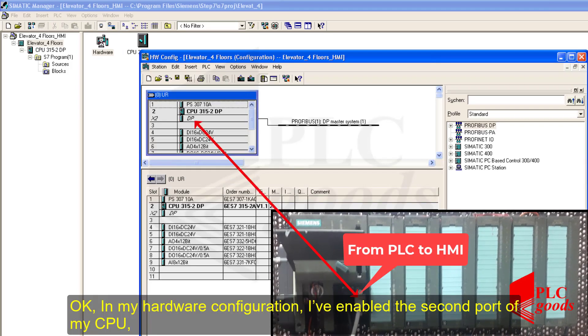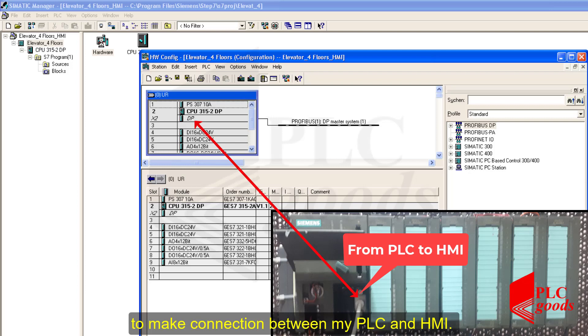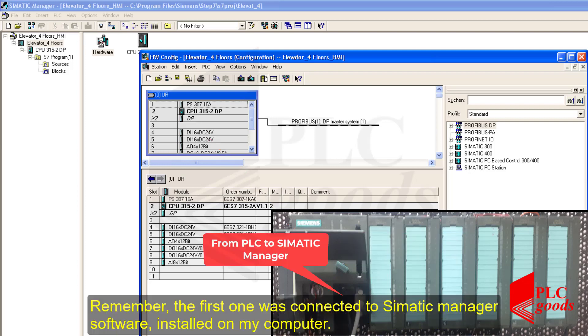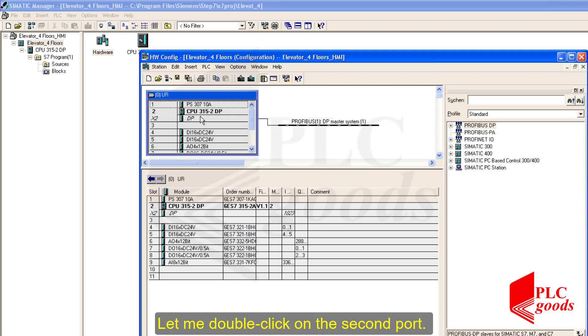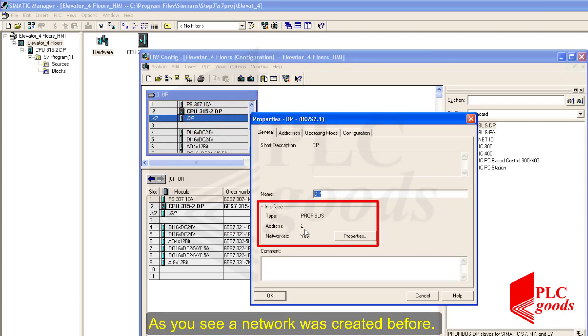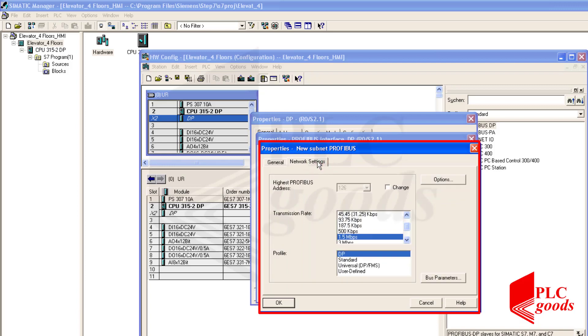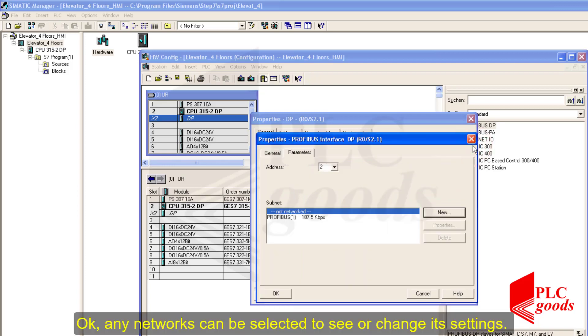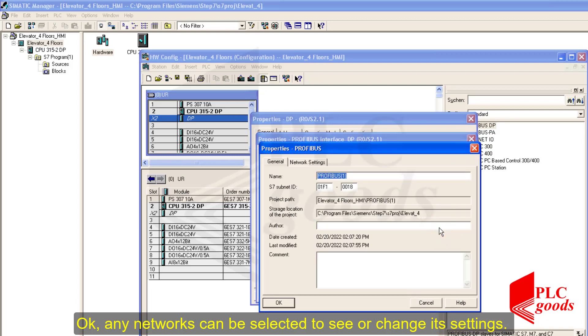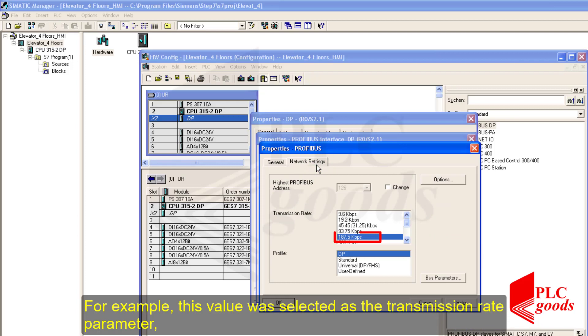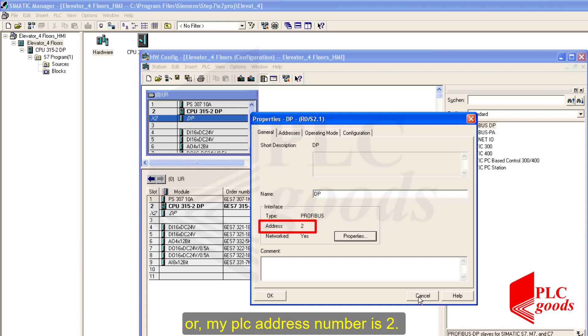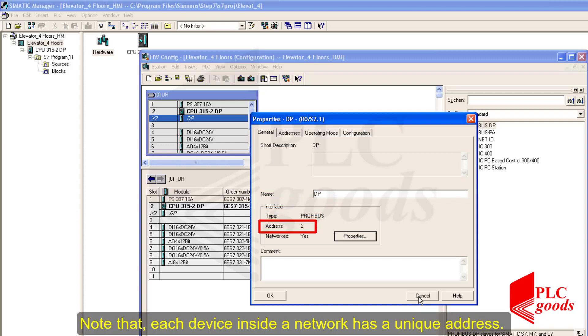In my hardware configuration, I've enabled the second port of my CPU to make a connection between my PLC and HMI. Remember, the first one was connected to the SIMATIC Manager software installed on my computer. Let me double-click on the second port — as you see, a network was created before; otherwise you can click the new button to create a new network. Any network can be selected to see or change its settings. For example, this transmission rate was selected for my network, and my PLC address number is 2. Note that each device inside a network has a unique address.